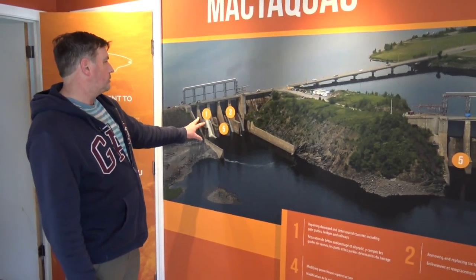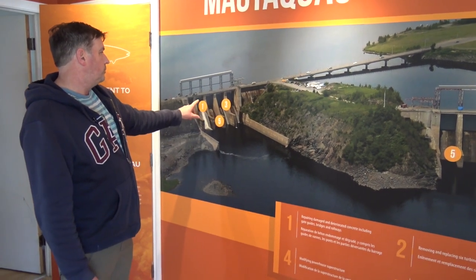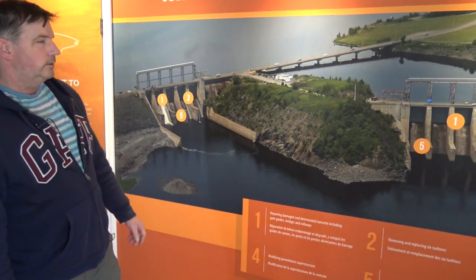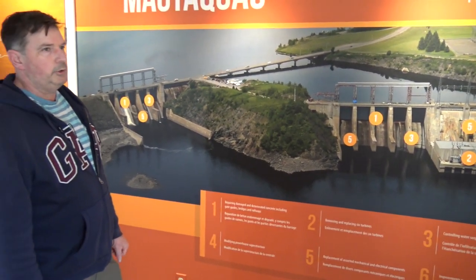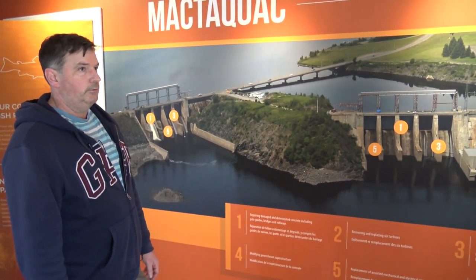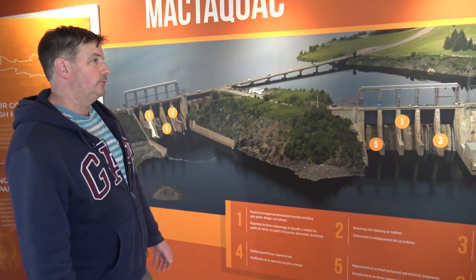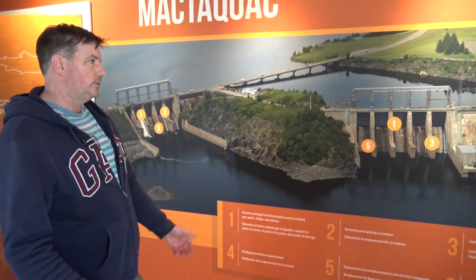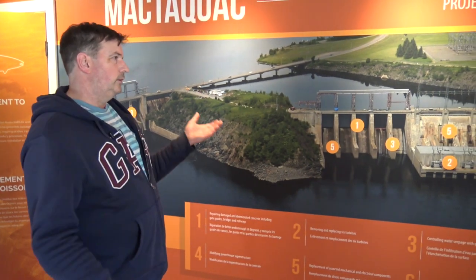As you probably notice right here, these are what they call diversion spill gates, and some of them are open right now — I think number two, number four, and number five. They let the water come through because there's too much water. To run all six units at full load, you need about 80,000 to 84,000 cubic feet per second. Right now, I think this morning it was 220,000 cubic feet per second, so we've got all kinds of water to run a heavy load. It causes some issues too if you get too much water coming through, so you have a different differential.